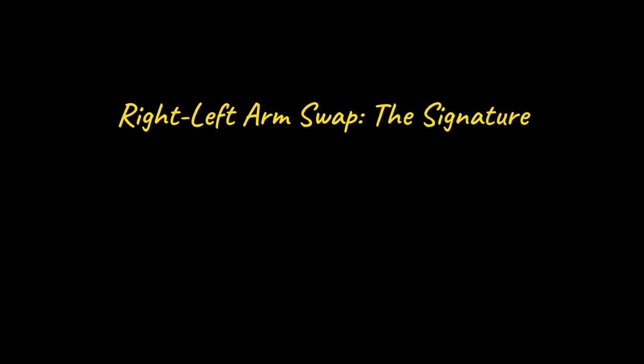Lead I and AVR look at the heart from opposite directions, making them electrical mirrors of each other. Understanding this reciprocal relationship is the key to spotting one of the most common errors in EKG acquisition. In normal sinus rhythm, atrial depolarization travels from the SA node downward and to the left, toward the left arm. Because lead I uses the left arm as its positive pole, this produces an upright P wave. Because AVR uses the right arm as its positive pole, that same wave moves away from it, inscribing an inverted P. When the right and left arm cables are swapped, every voltage in lead I flips.